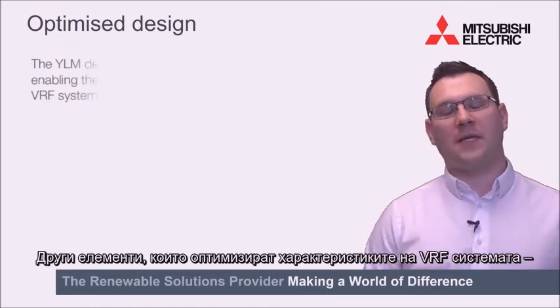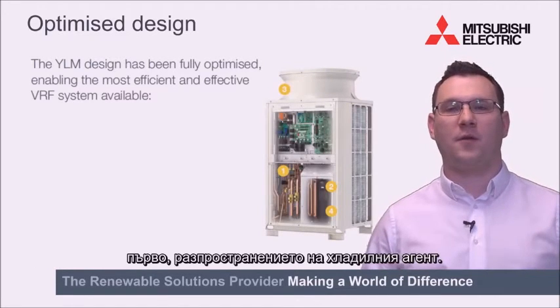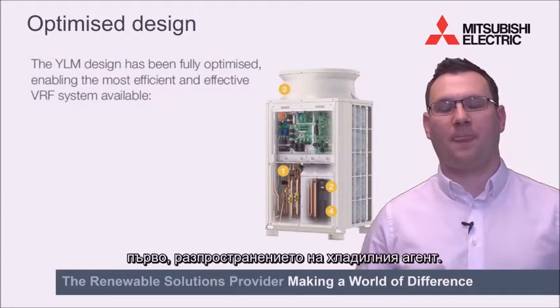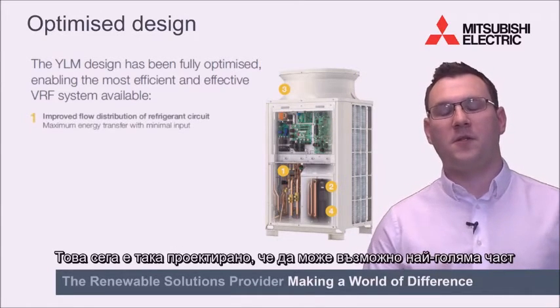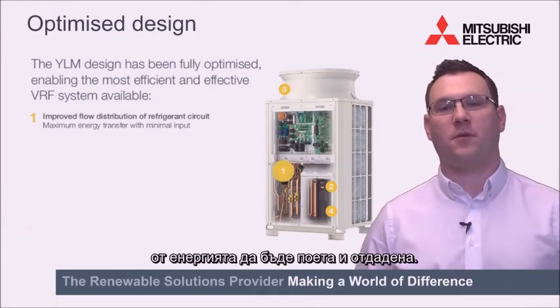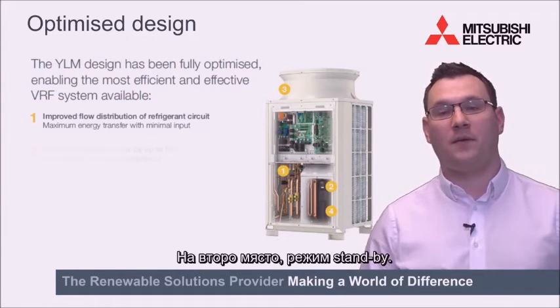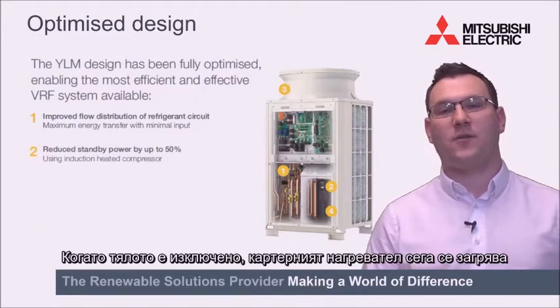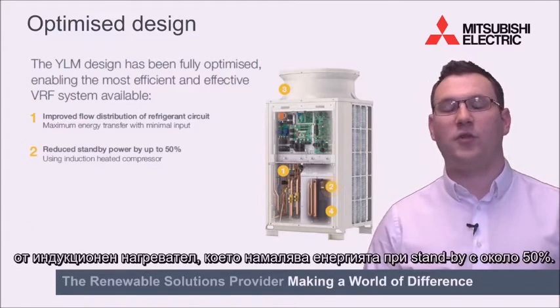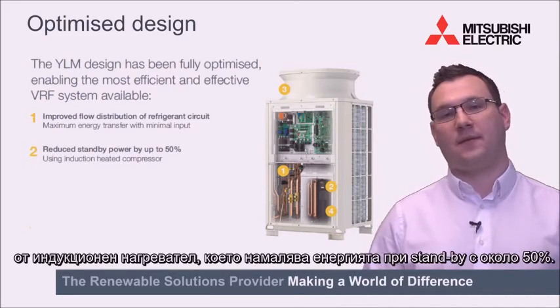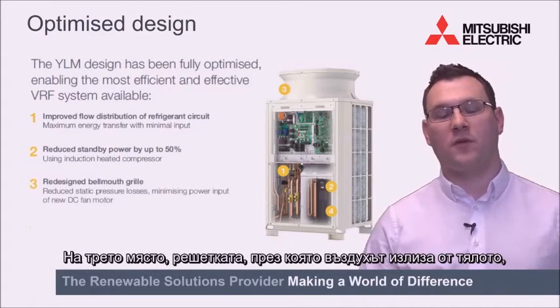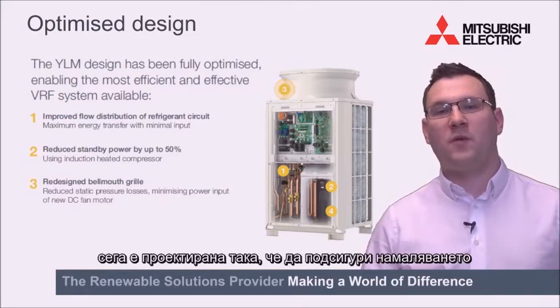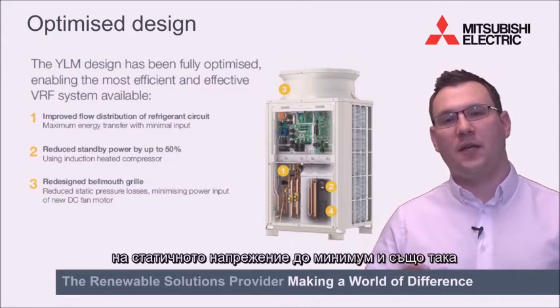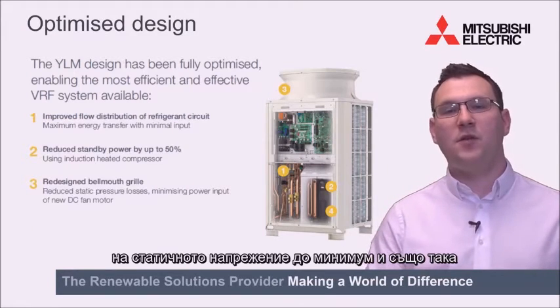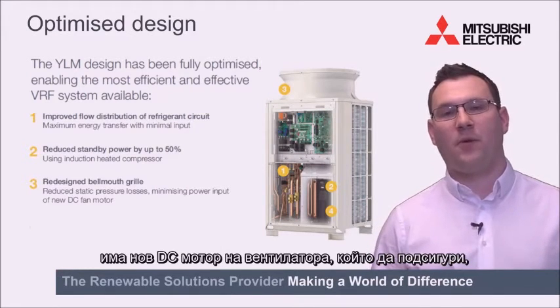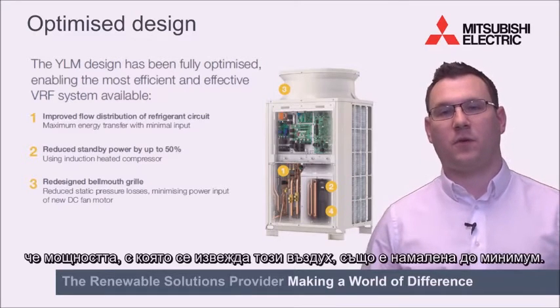Other elements which have optimised the design in the VRF system firstly include the distribution of the refrigerant. This has been now designed so that the most amount of energy can be absorbed and rejected as possible. Secondly, standby power. So when the unit is off, the crankcase heater is now heated via an induction heater, reducing standby power by around 50%. Thirdly, the bell mouth grille, so where the air comes out of the unit. This has been redesigned to ensure static pressure is reduced to a minimum, and there's a new DC motor on the fan to ensure the power input to push that air is also reduced as much as possible.